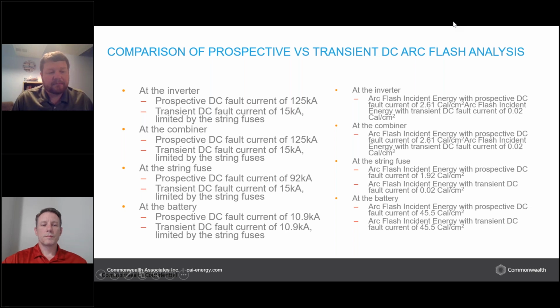All right, so what we wanted to do is a one-to-one comparison. This is a nice analysis to show, okay, what is the prospective fault current? And in this case, what happened when we put in these fast-acting fuses? If we didn't have the ability to have these fast-acting current-limiting fuses, we would have to use prospective fault current. And mind you, arc flash is generally guided by an I²T function. Now, it's mitigated a bit by other factors, but in general, that's true.